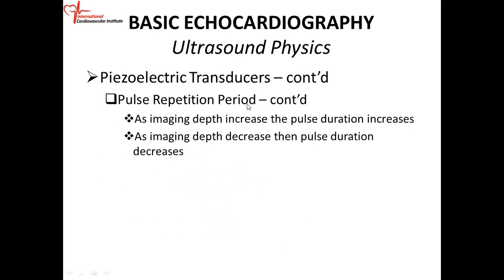So the pulse repetition period, as the imaging depth increases, the pulse duration. So just common sense, if you image a structure that is deep in the body, then the imaging depth increases and the pulse repetition period also increases. Okay? And as the imaging depth decreases, the pulse repetition period decreases. All right?